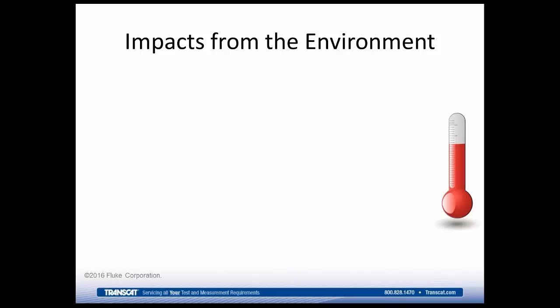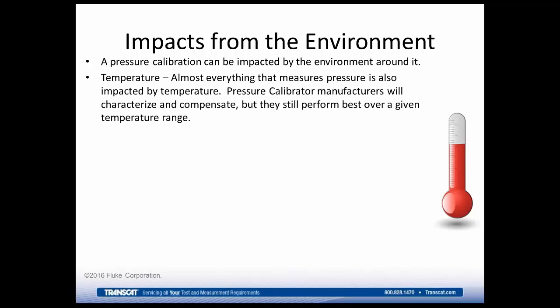We also need to look at the impacts from the environment on our calibration. For example, temperature. Almost everything that measures pressure is also impacted by temperature. So a pressure calibrator manufacturer, such as Fluke, will characterize and compensate our pressure measurement devices, our calibrators, so that they can work at different temperatures. But they'll still perform best over a given temperature range. Depending upon the device, that may be 0 to 50 degrees Celsius, or perhaps even wider, or it may be as limited as, say, 18 to 28 degrees Celsius.